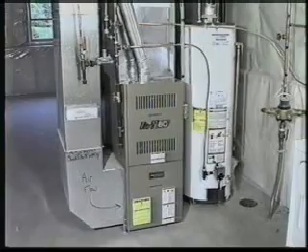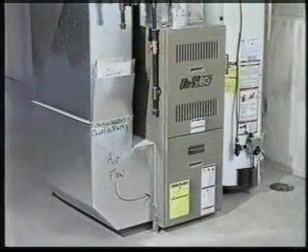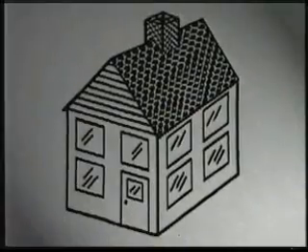To the homeowner, the equipment room appears to supply a sufficient amount of air for the appliances to burn efficiently. Fact: the furnace shown here used 100% of the air in this room for one heating cycle. This room is now at a negative pressure and must rob air from the rest of the home for each succeeding cycle.